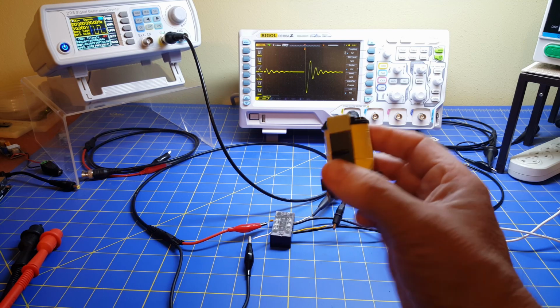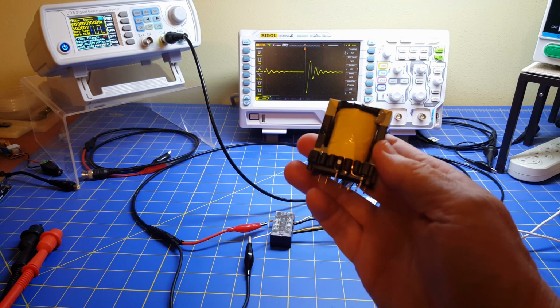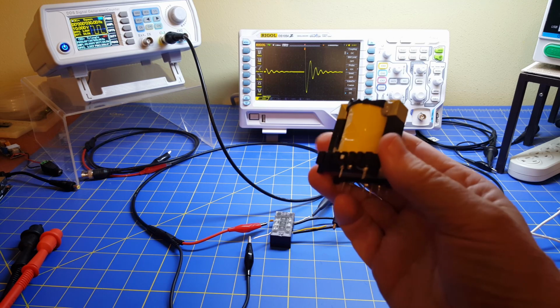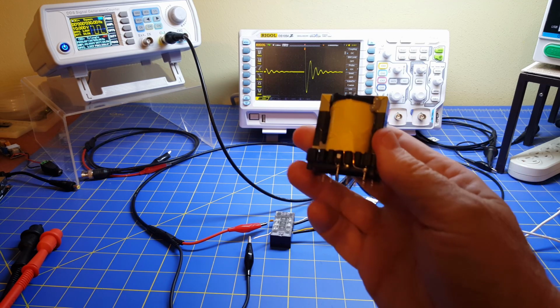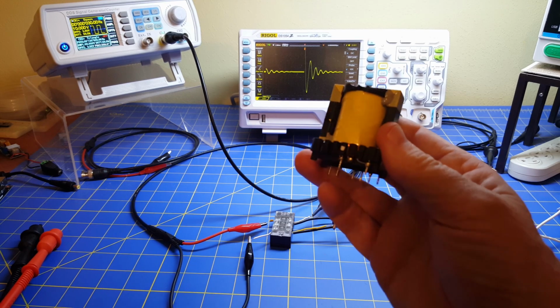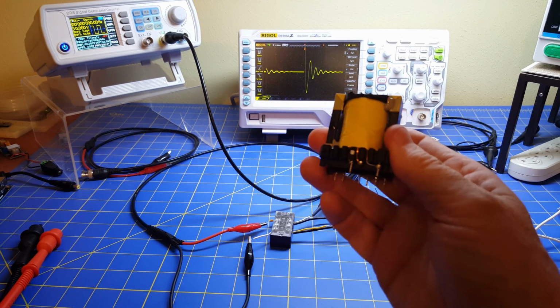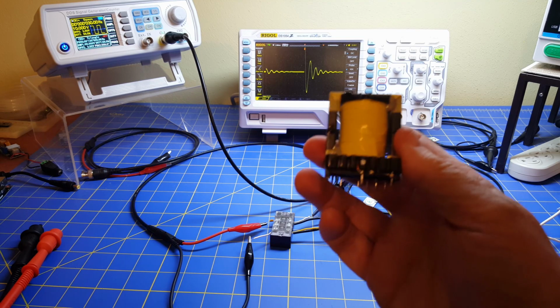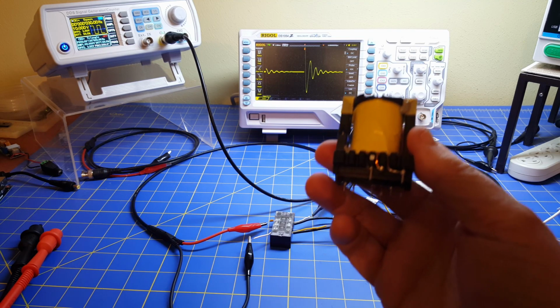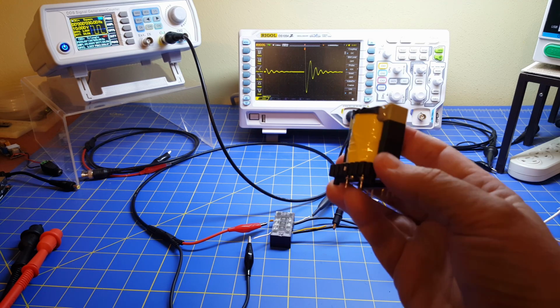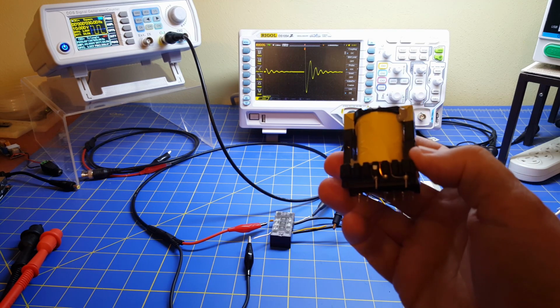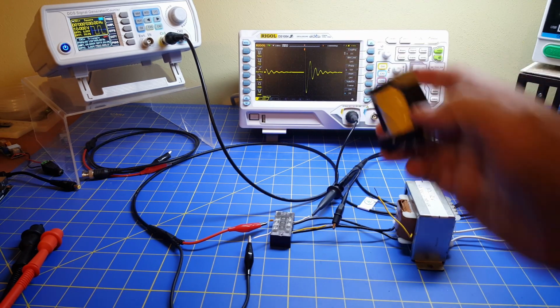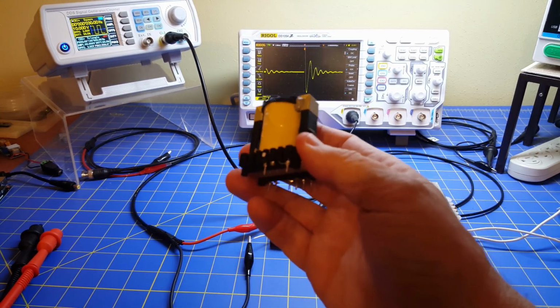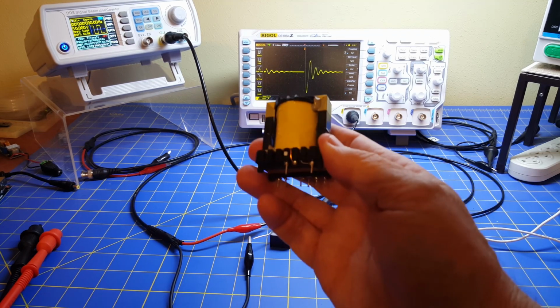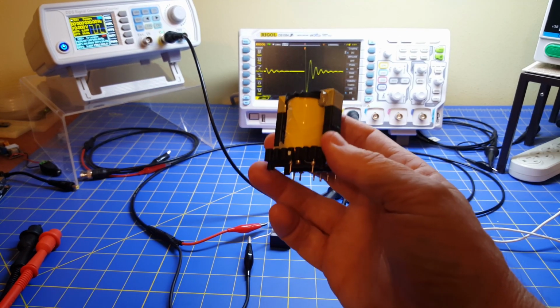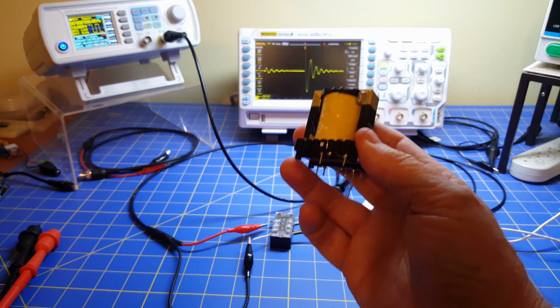We looked at modeling that in LTSpice to better understand the characteristics of the transformer. We also looked at simulating a short circuit and applying it and looking at the number of rings. At the end of the discussion, we came up with the concern that it's really very complicated and there's a lot of things it depends on. The number of rings you get on a scope trace like that depends on a lot of different things. So you really need to be wary about just merely applying a ring tester to a transformer and thinking you know whether it's good or bad.